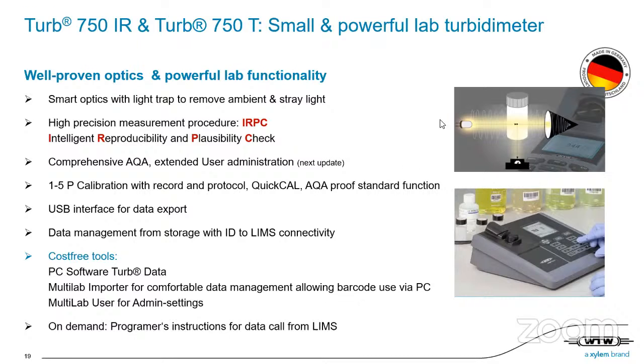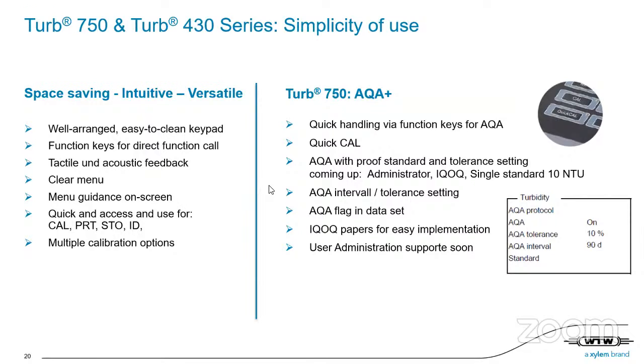So we have, as I said, the same optics. We do have a high precision reproducibility and plausibility check, which is also in the small meter, but we do have a big AQA with an extended user administration coming, a 1 to 5 point calibration, and quick cal and calibration proof, which is important for bigger labs and service labs. We have a USB, many data management options, and all the cost-free tools, including a PC software. And we can also hand out programmer instructions if you are a bigger organization and you have a special LIMS system and your programmer wants to pull the data from our meters. You can reach out to Analytic and we will hand that out for them so that you can use it in your labs.